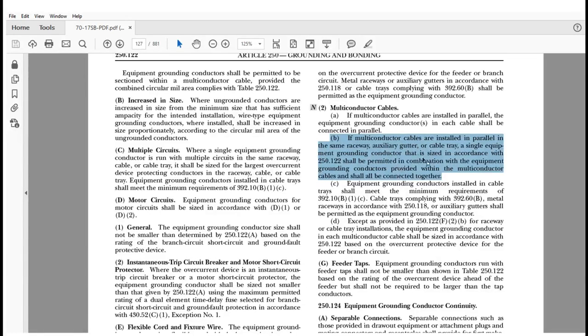But if you don't do it this way, don't forget that whether I run it in a raceway or a cable tray in a parallel application, if I run multi-conductor cables in it, you're going to make sure that equipment grounding conductor is sized properly. If they're running parallel, and that overcurrent protection device is going to be obviously larger to protect that parallel application than it would have if it was a single cable, then you're going to have to size that equipment grounding conductor full size. All right, I beat that one to death, man.